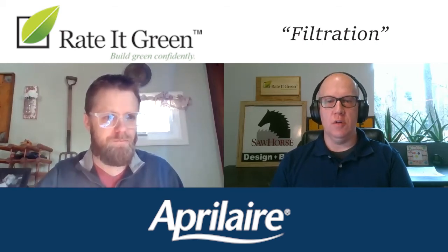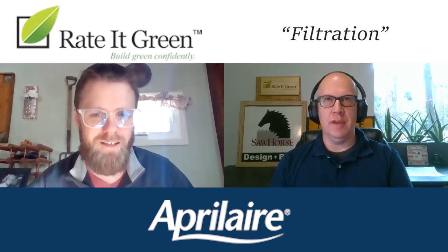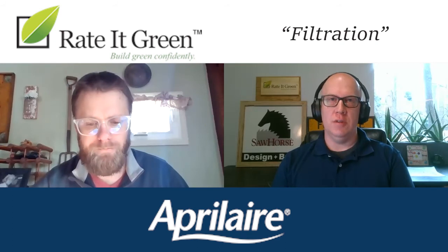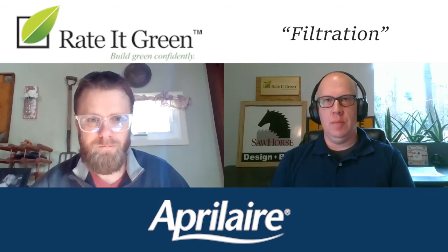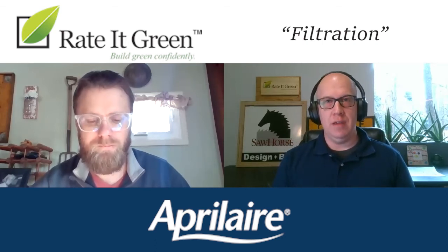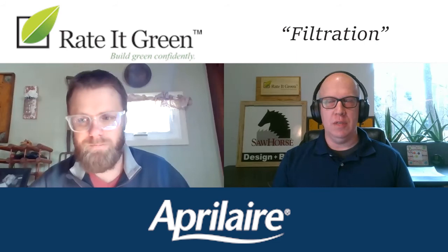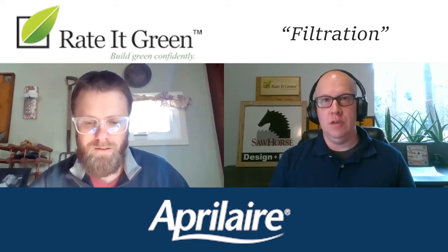And I think that's the irony of all this. You mentioned that cheap blue filter, which is pretty much good for catching birds and rats from going through your system — that's probably your most energy-efficient filter because it allows so much airflow. But when you restrict the airflow, if you just put a HEPA filter in that same one-inch slot from a big box store, while you're definitely helping with the filtration, what you're doing with that static pressure drop is putting extra strain on the fan. Because of that extra strain, your energy bills are going to go up. Most people don't realize it — they think they're doing a good thing. But you may burn the fan out and void the warranty.